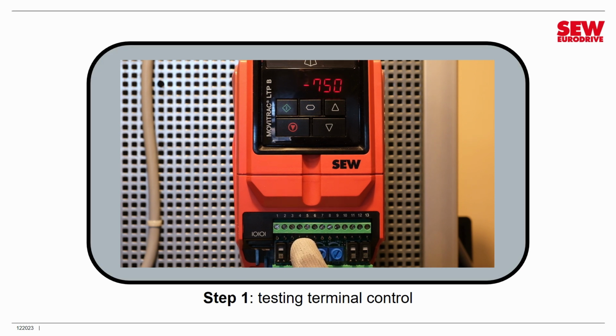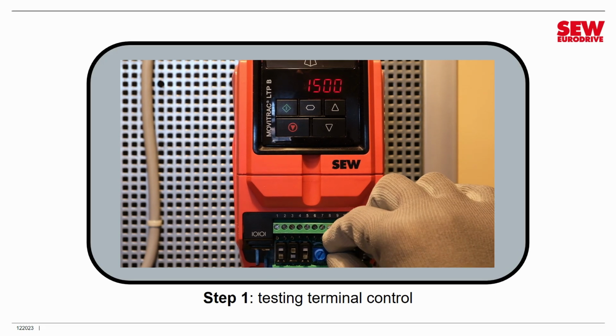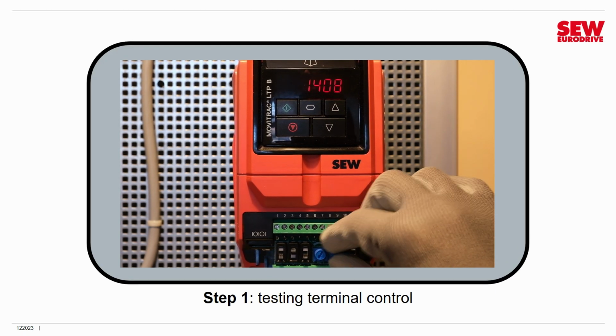So I'm going to engage it here. And you can see we're going to go to 1500 RPM clockwise. And now I'm going to turn the potentiometer all the way up to select the second preset, which should be 500 RPM counterclockwise. And it is. Now let's go back to field bus control by turning digital input 3 off. We're back to 750 RPM counterclockwise.